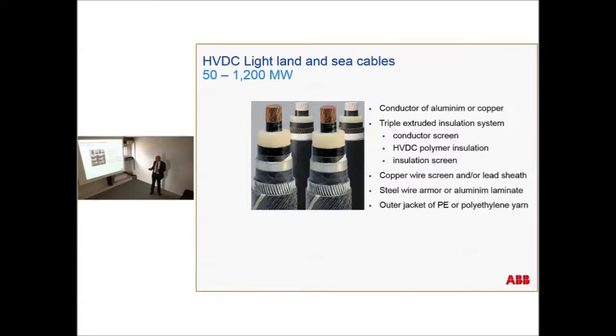I will go through the system here, but they are normally triple extruded insulation. You have the conductor, you have the conductor screen, you have a polymer insulation, and then you have an insulation screen. Then you normally have a lead sheath. Then you finish with a steel armoring and an outer jacket to protect the cable.